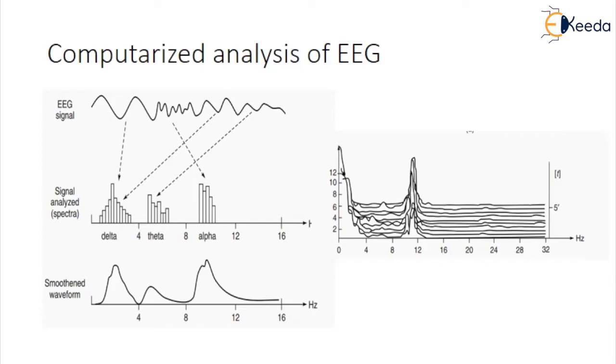The most common number reflecting EEG amplitude is the total power of the EEG spectrum. Due to the microvolt amplitude of EEG, power is either in nanowatts or picowatts. The power spectrum is calculated by squaring the amplitudes of the individual frequency components. The power of the individual frequency bands are also commonly used as expressed as an absolute or percentage of total power.